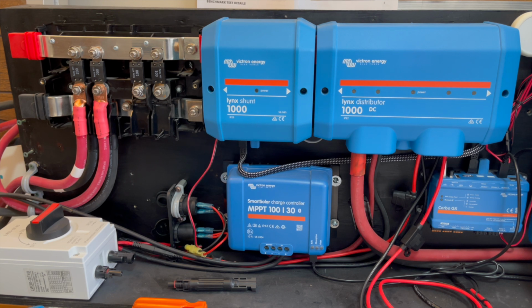It has to have a bus bar. I don't want cabling going from one battery to the next battery to the next battery. Even though the BMS talks to each other in this network, there can still be issues of balancing voltage and state of charge. So a bus bar is a must. If the server rack doesn't have one and the battery that I'm looking at doesn't support it, it's off my list.